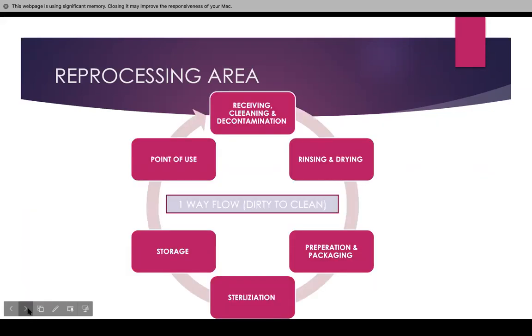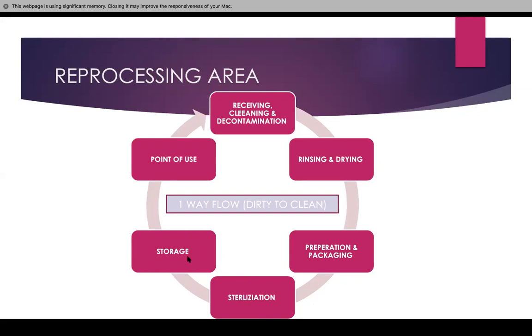The reprocessing cycle must be a one-way flow — it has to go from dirty to clean. First, you have the receiving, cleaning, and decontamination. Then you rinse and dry. Then you prepare and package. You send it off for sterilization in the autoclave. Then it goes to a storage area on the clean side. You cannot have anything dirty on the clean side — that is the whole point of a one-way flow.